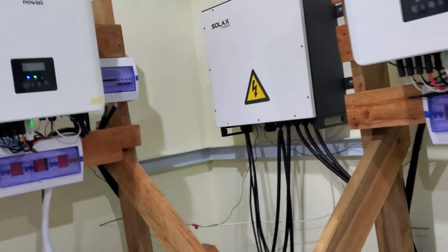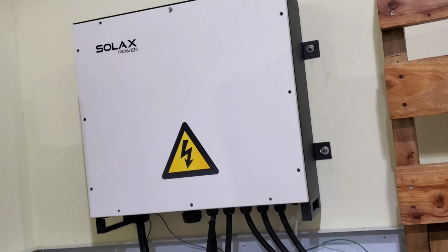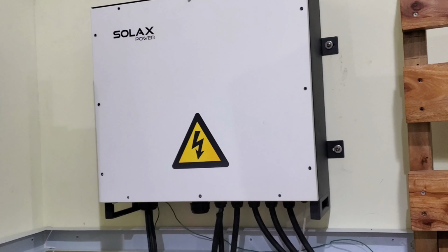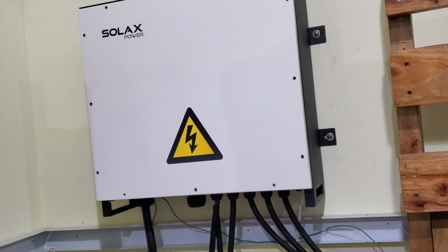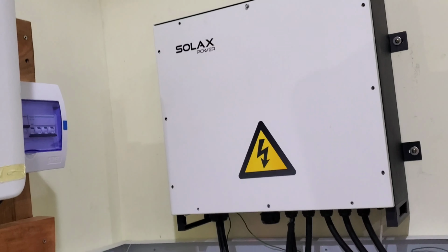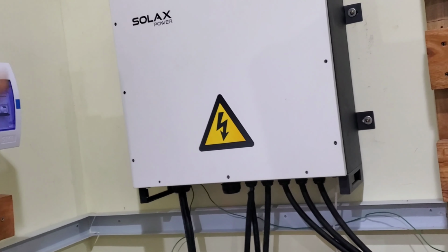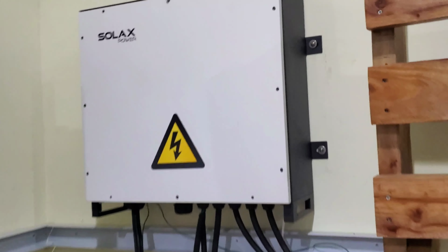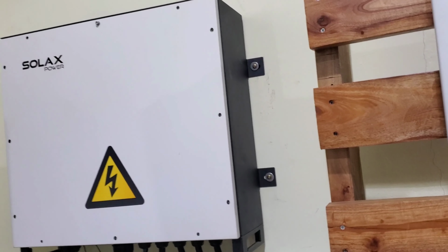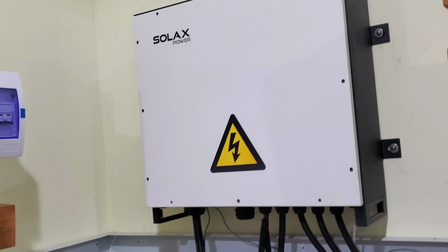That's one thing I didn't explain to you, the EPS parallel box. This big device here weighs about 35, 40 kg, 42 kg actually. It has multiple contactors and bus bars. It has our input and our output. It has communications between the inverters, the master inverter, and it, and it shows all the inverters that are connected. The EPS parallel box has all our connections coming in. It has contactors to switch between the grid or a gen and our system.